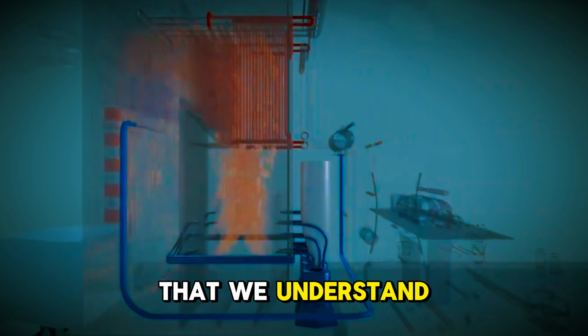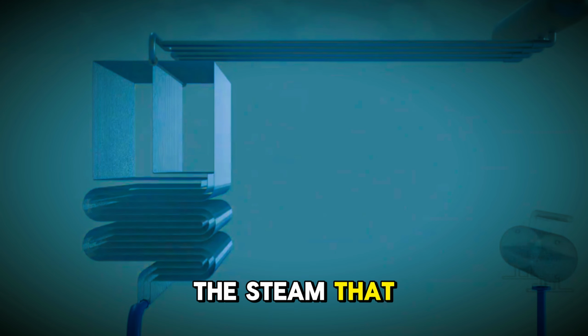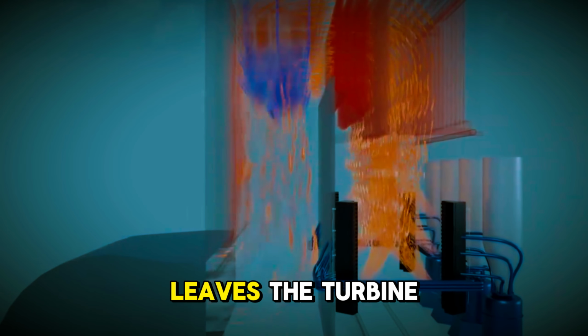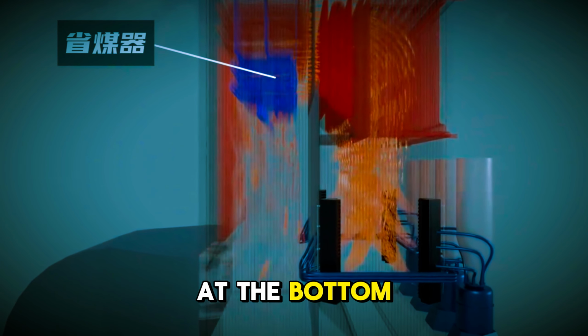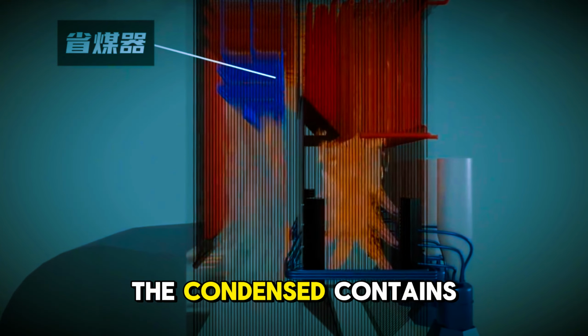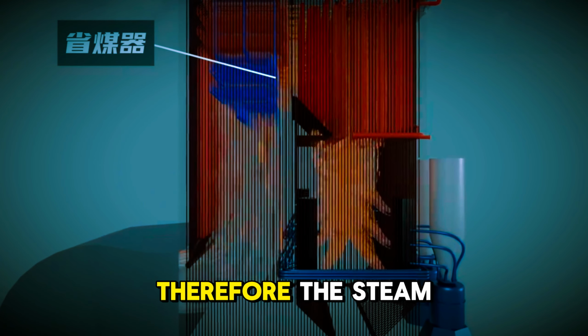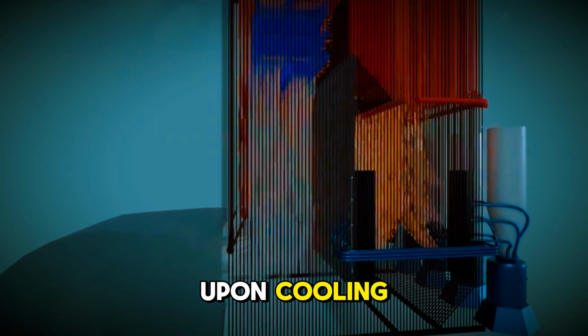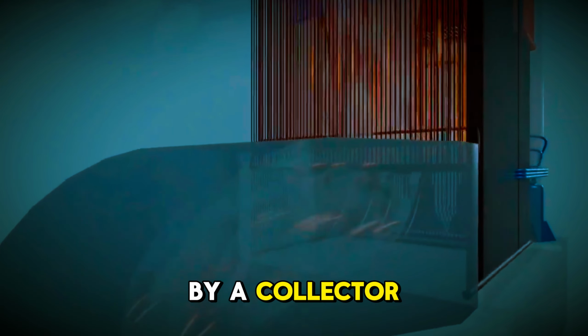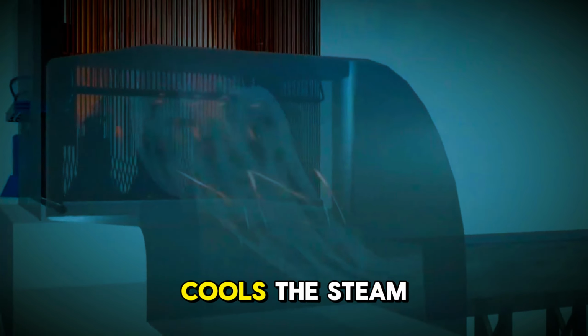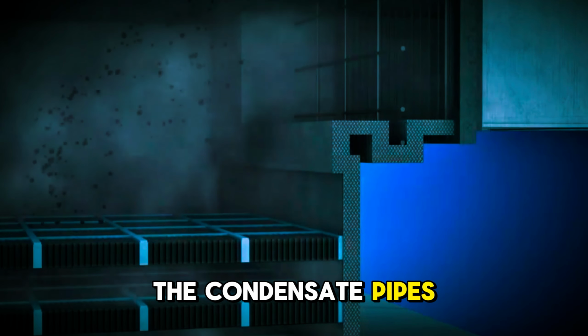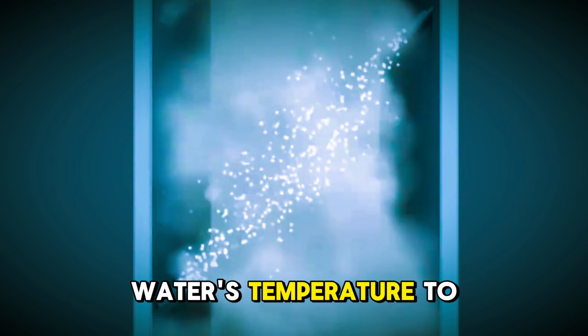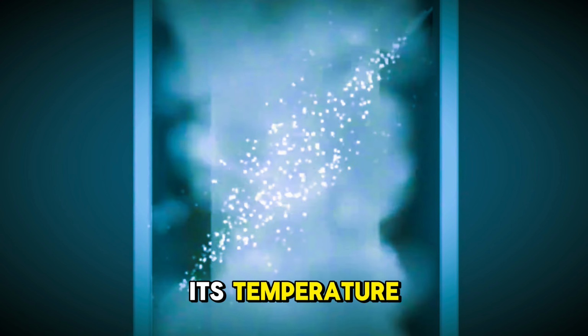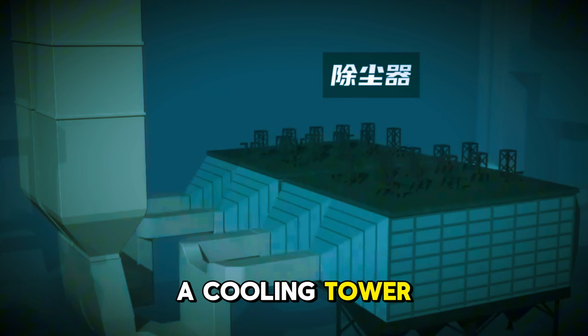Now that we understand the principle of power generation, let's return to the low-pressure turbine. The steam that has completed its work in the low-pressure turbine is actually not wasted. This steam leaves the turbine and then enters the condenser at the bottom of the low-pressure turbine. The condenser contains circulating cooling water. Therefore, the steam condenses into water upon cooling, and the condensed water is collected by a collector at the bottom. As the condenser cools the steam, the water in the condenser pipes absorbs heat, causing the cooling water's temperature to become very high. To lower its temperature, the cooling water is sent to a cooling tower for cooling.